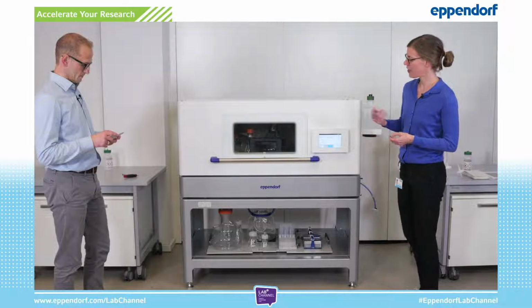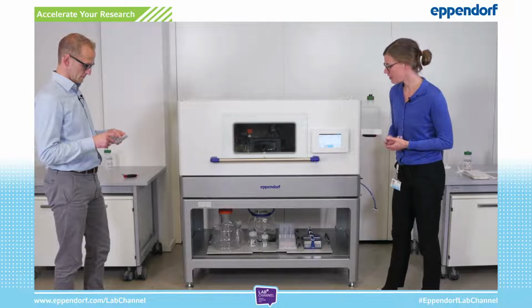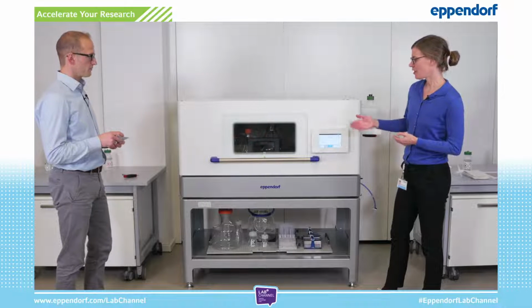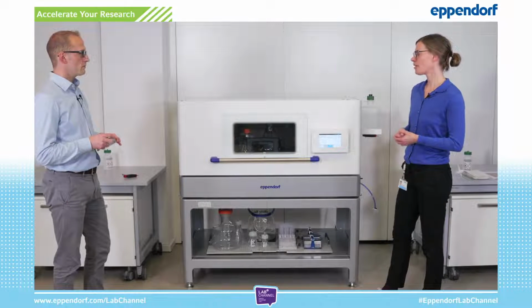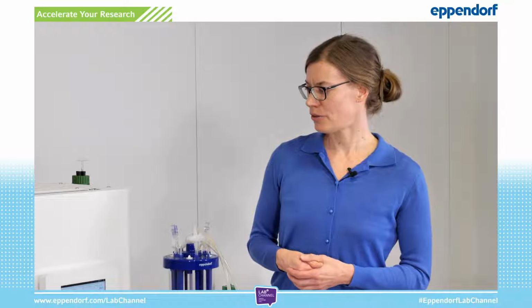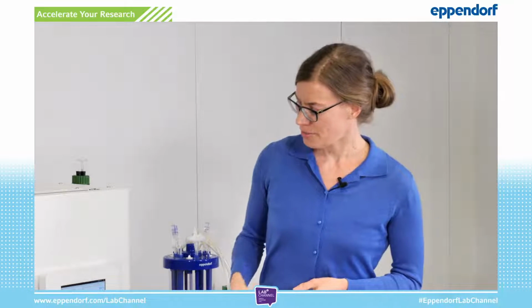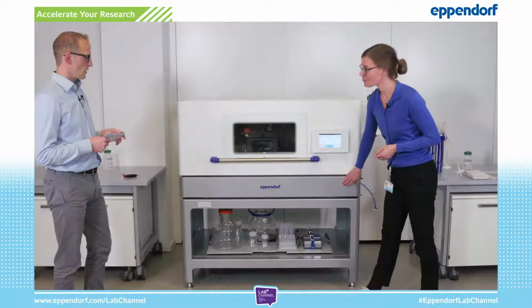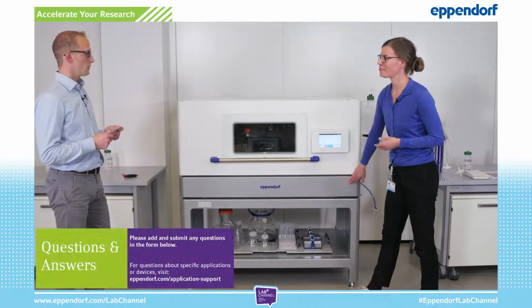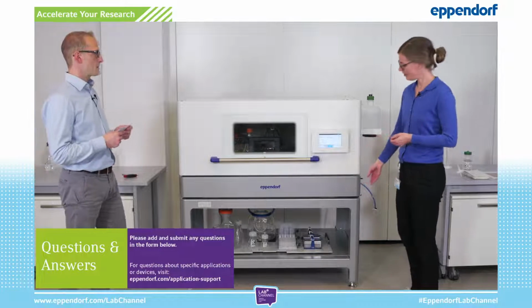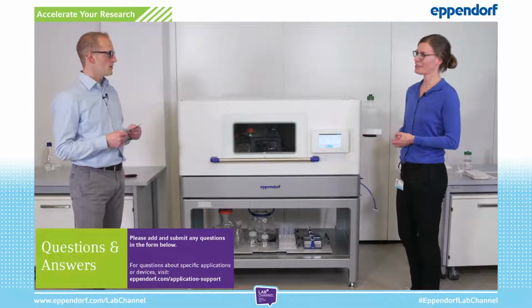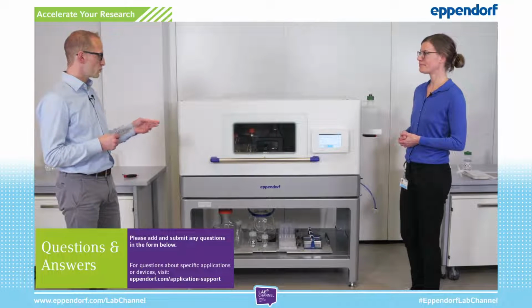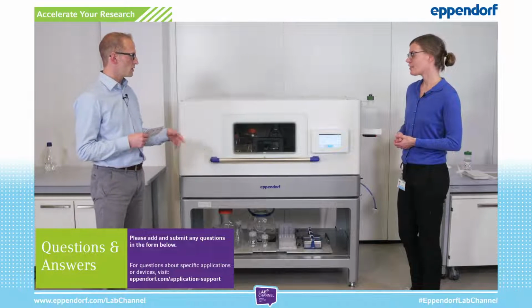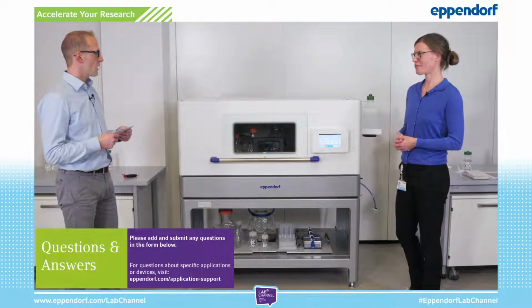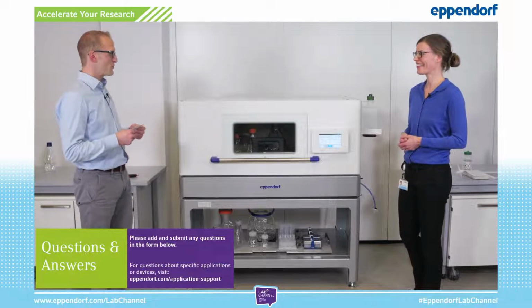So the drive for the agitation is placed outside the chamber to not have any influence on the chamber environment and also to not cause any vibrations there. Plus, this is a drawer, so service, not the customer, can open this and get the drawer out for easy servicing. So the drive wheel is also down there? It's all down there. We will also take a look in the chamber. I will be patient then.